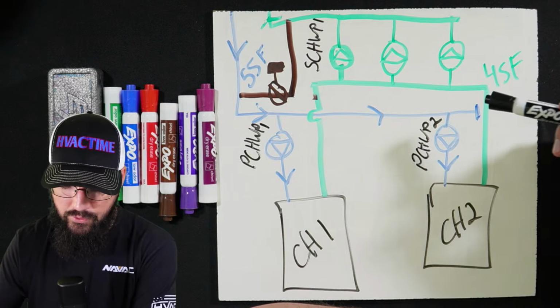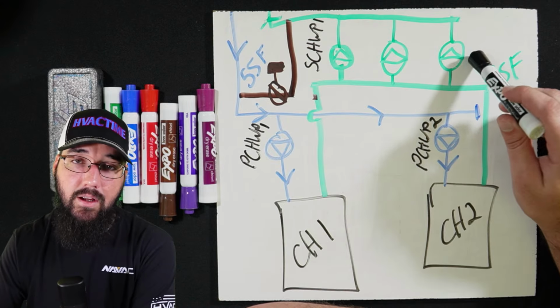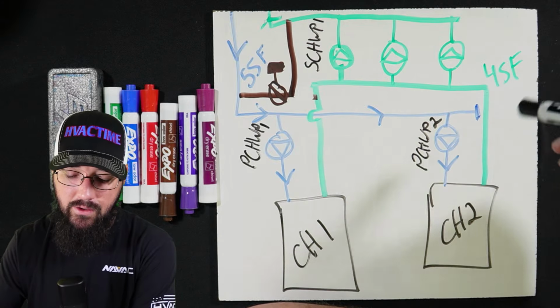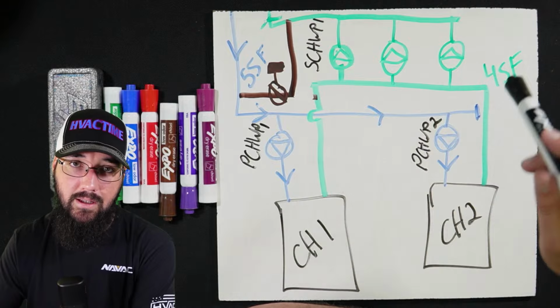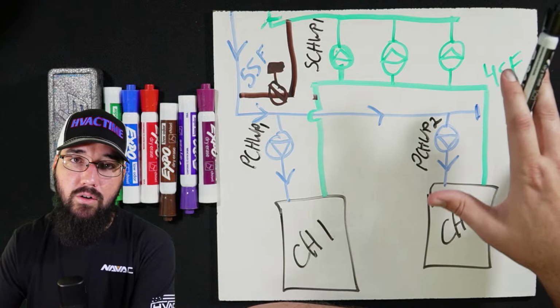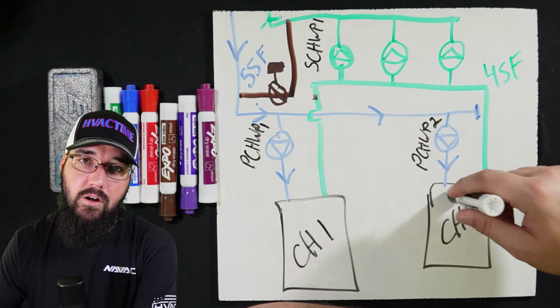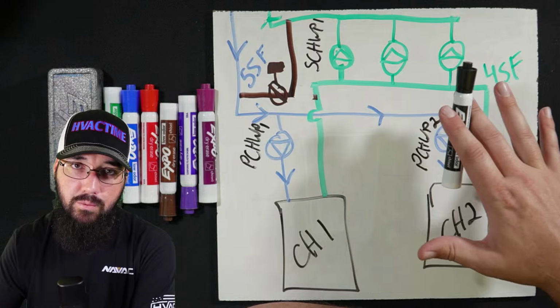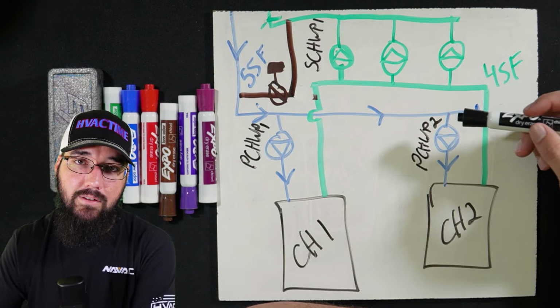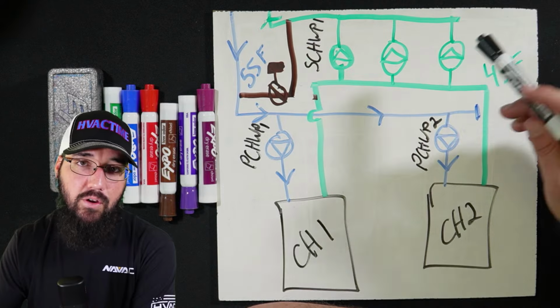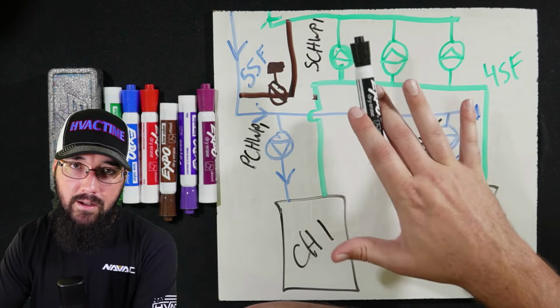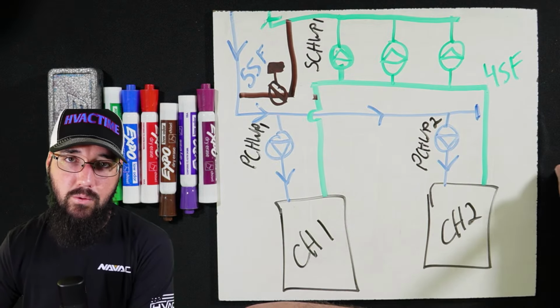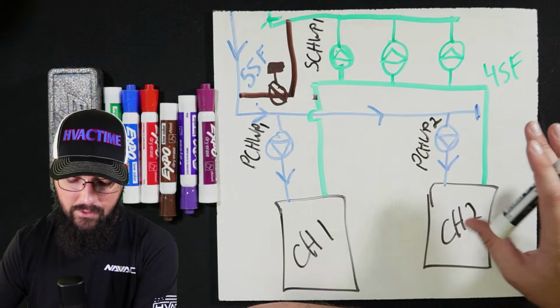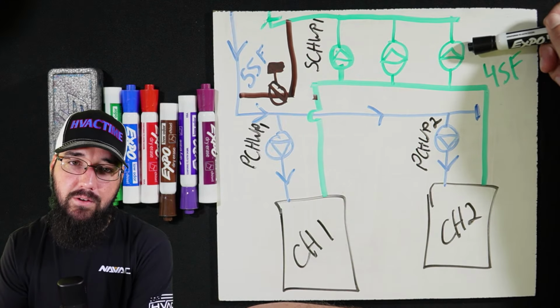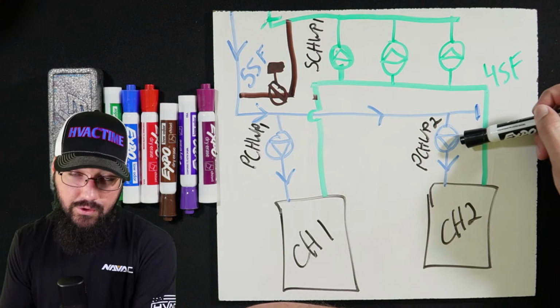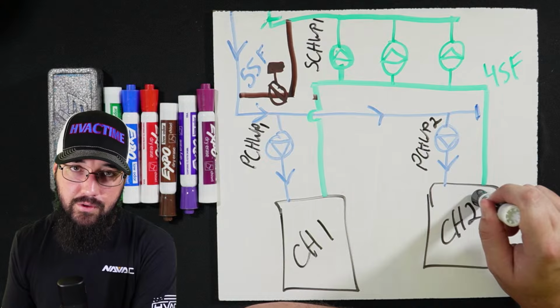So the plant control system will turn on the primary and the secondaries together, get the plant stabilized. Even though we're not making set point, it's not the point at that point in time. It's just a matter of get the water stabilized. Then we'll start turning the chiller on and start letting the loop pull down from there once we have the loop stable. Because if we try to turn all these on simultaneously, a lot of weird stuff can happen with the flow and the pressures and trying to stage up and get the loop balanced. It's going to just freak the chiller out to all ends. So that's not a good path. Okay. These are going to stage based off of the loop load. These are just on. They're maintaining flow through the chiller.